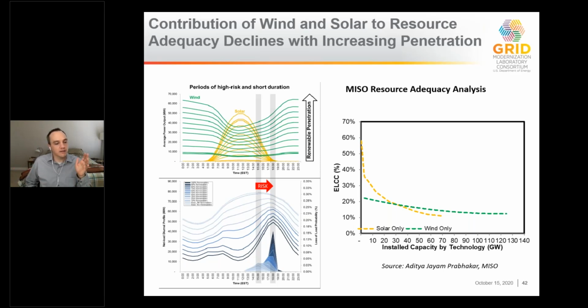If you take that low penetration level, look at solar production during times of high risk, and calculate its contribution to resource adequacy targets, shown on the right, you'd find a capacity credit for solar as high as about 60% of nameplate capacity. So with 100 megawatts of PV, you might count 60 megawatts toward your resource adequacy targets. Wind, under the same conditions, would get only about a 20% capacity credit.